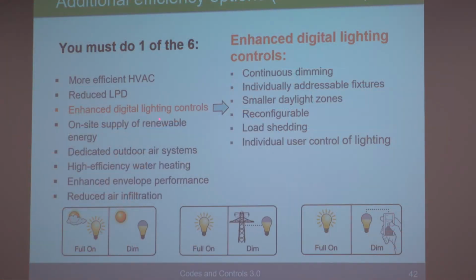Okay, so IECC has a section called optional energy efficiency incentives, all right? And basically all projects have to comply with one of these. One of them is reduced lighting power density. So if you do 10% lower the watts per square foot, you're done.